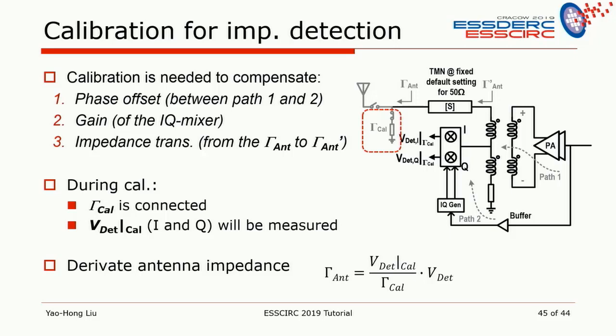So what we do is propose a calibration impedance. We first load it here and then do the measurement again. We will get a V detection calibration, and then we use this voltage and this equation. Then we can get the actual impedance of the antenna at this node. So this is how we calibrate the whole system such that we can get a precise impedance measurement.